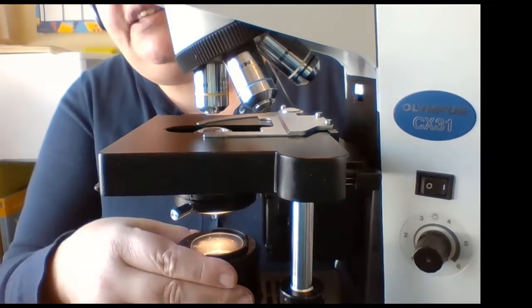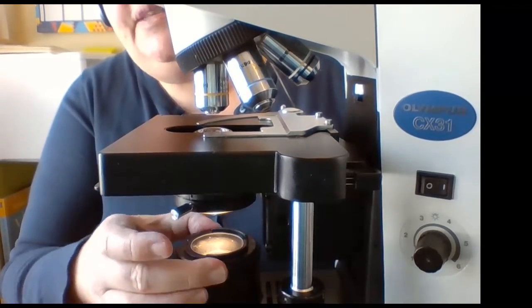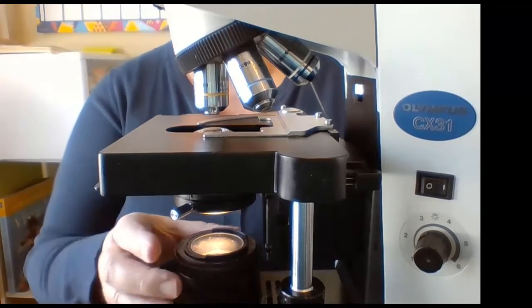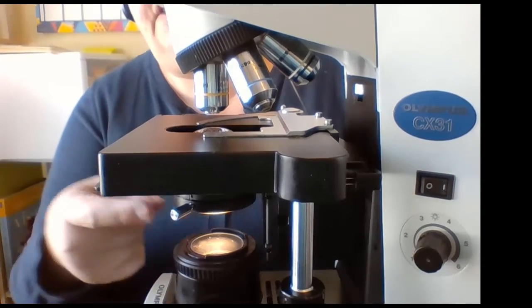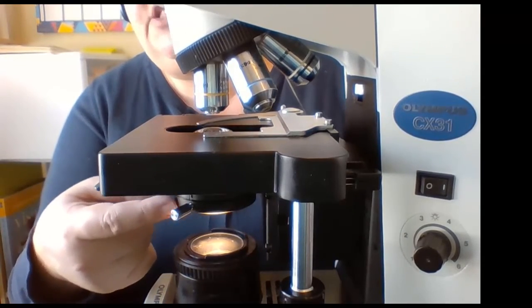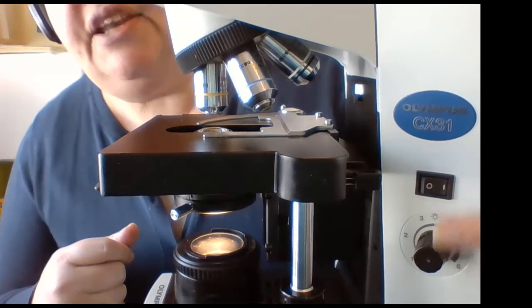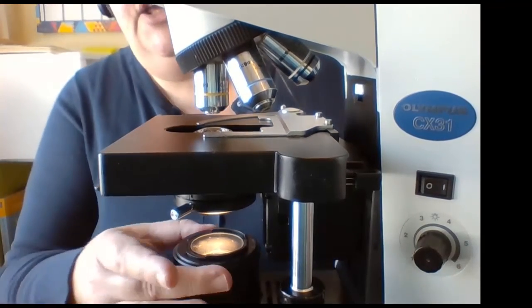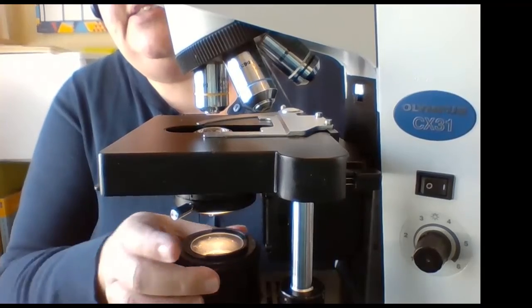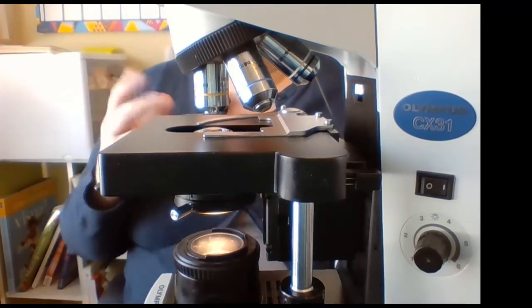This is our actual light source. You want it to be all the way open. You want to control the light that comes out of here by controlling the condenser and the iris diaphragm and controlling the light intensity. You won't ever turn this except to make sure that your light is all the way open.